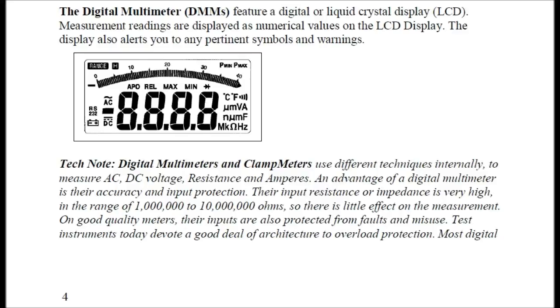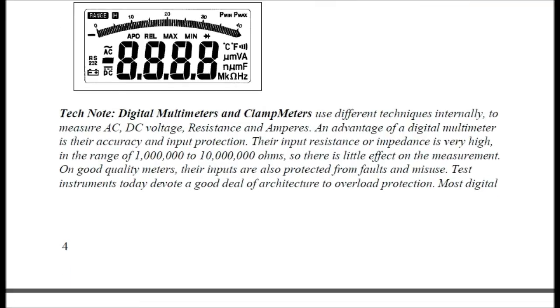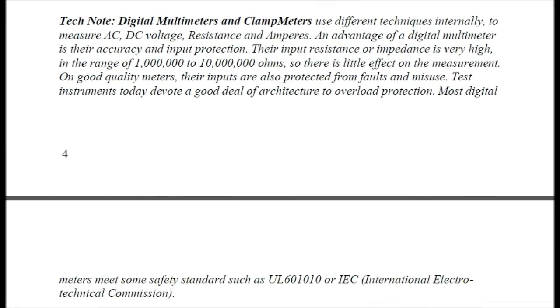Tech note: digital multimeters and clamp meters use different techniques internally to measure AC voltage, DC voltage, resistance, and amperes. An advantage of a digital multimeter is their accuracy and input protection. Their input resistance or impedance is very high, in the range of 1 million to 10 million ohms, so there is little effect on the measurement. On good quality meters, their inputs are also protected from faults and misuse. Test instruments today devote a good deal of architecture to overload protection. Most digital multimeters meet some safety standard, such as UL 601010 or IEC — International Electro-Technical Commission.